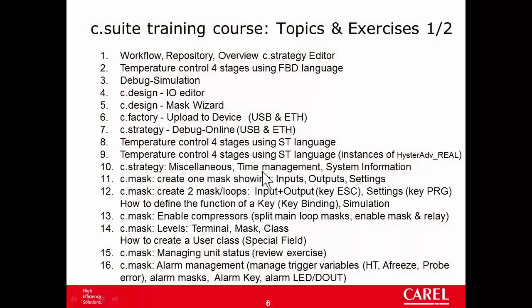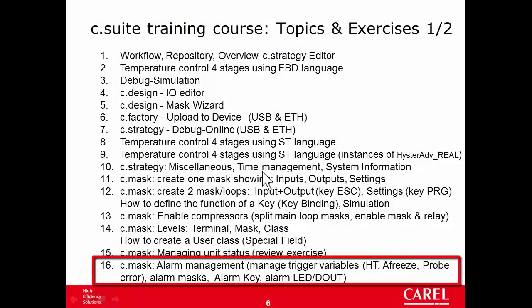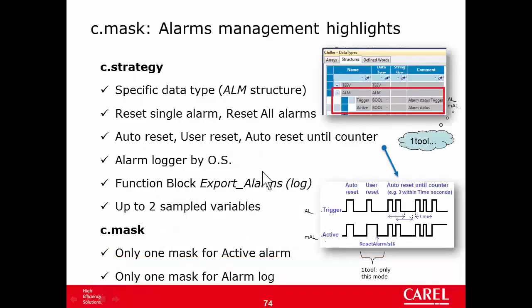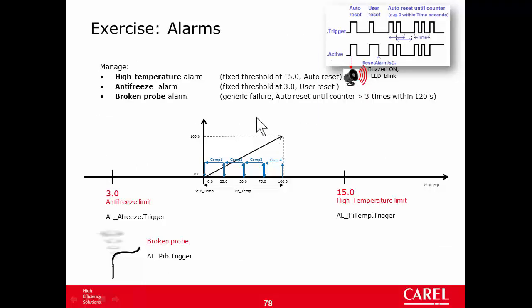In the last part of this very long tutorial, we are ready to manage alarms from the practical point of view. Since there are three types of reset — auto reset, user reset, and with the counter — we can manage three alarms, one for each type. We can manage the high temperature alarm with the auto reset, antifreeze with the user reset, and broken probe with the counter.